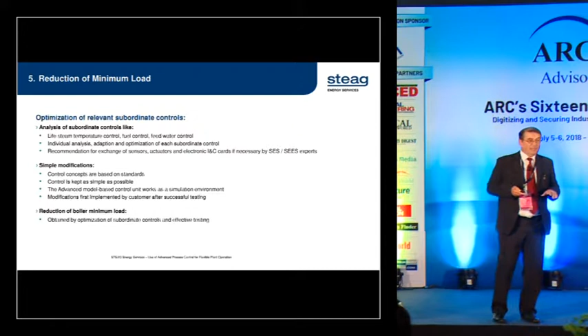to ensure that the operation will be safe. And of course, we have to elaborate the concept of the controls, make the testing, and only after very extensive testing can we ensure that the unit can run with a really low load. If we want to minimize the load, especially with once-through boilers, we have to look at whether the boiler furnace will operate in a stable way. We have to look at the live and reheat steam temperature, and take care that turbine ventilation will not happen. About the flame stability, I already talked. And we have to look at all the interlocks which prevent the boiler from being run at the minimum defined load.